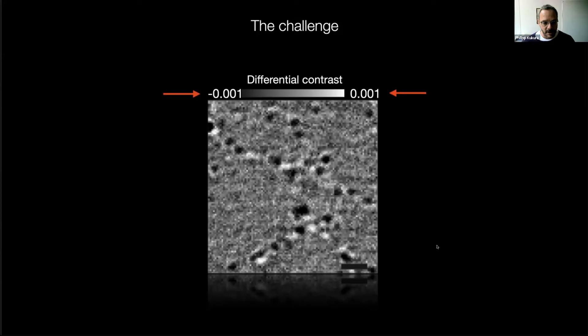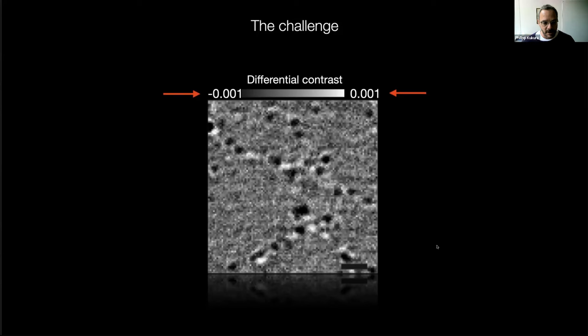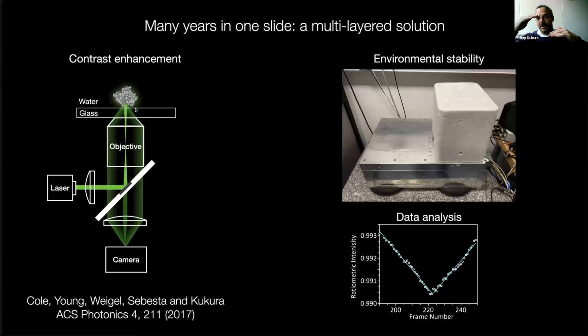This is one of those slides where people have spent many years working very hard and you put it all in one slide and talk about it in 40 seconds. Essentially, one critical aspect is that we slightly changed the way we do the illumination and detection, which changed the ratio between light scattered by the protein and light reflected at the interface. If you decrease the amount of reflected light while keeping the scattered light constant, your contrast gets bigger.